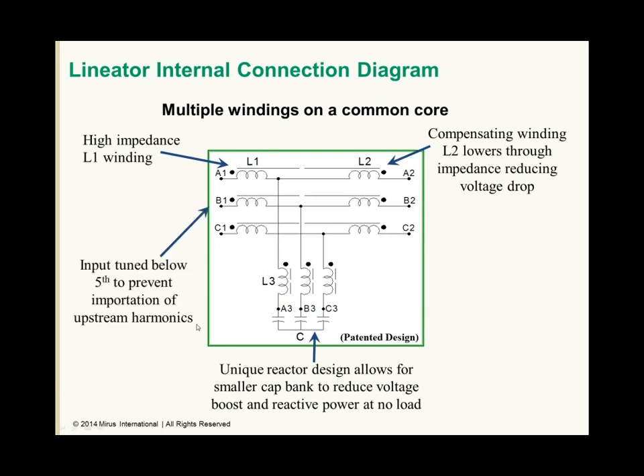On the input side, we make sure that we're tuned safely below the 5th harmonic. Therefore, pre-existing or background distortion that's a result of other loads on the power system will not be imported into the filter. And then on the output, it's tuned above the 7th to be most effective in filtering out the harmonics generated by the variable speed drives.